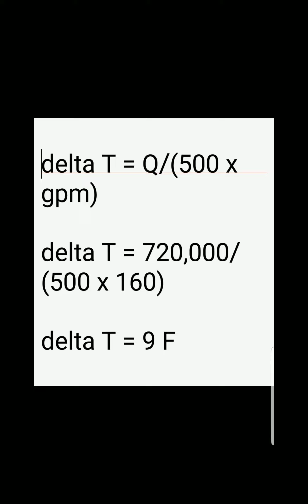And the second part is we are told to calculate the return temperature. So the return temperature is equal to delta T plus the supply temperature. And so we get the return temperature of delta T that we calculated equal to 9, and the supply temperature which was given being 45 degrees Fahrenheit. So we just add the two together, 9 plus 45, and we get return temperature of 54 Fahrenheit. That's the answer to the second question.